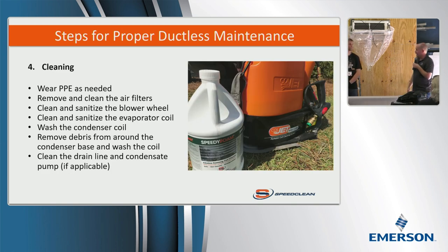All right, next, when you do your cleaning, you're going to definitely wear PPE. The biggest thing is safety glasses by far. Most of the cleaners we suggest using with this—really all of them that we suggest for coil jet and for ductless—are going to be essentially neutral cleaners: non-caustic, so non-acid, non-alkaline, or at least only mildly alkaline, and diluted appropriately to a mild concentration.